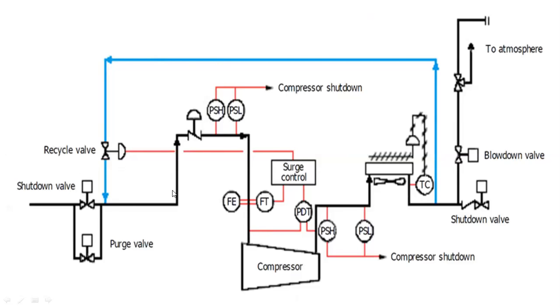Another example of control: by measuring the pressure level — sensing low or high pressure — feedback is taken from the exhaust discharge and given to the controller, which controls the suction. In between, we have a flow transmitter and flow element, pressure differential transmitter, because if the pressure level is high or low, the compressor can be shut down accordingly. We also have temperature control at the aftercoolers. This is a typical control system and process involved with compressors.